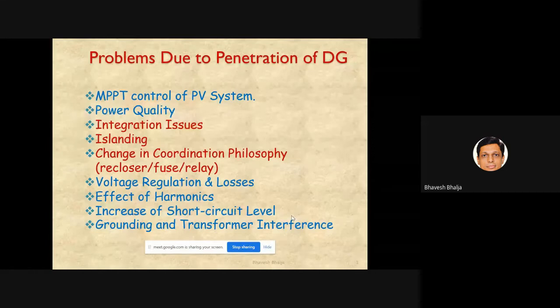The next issue is the increase of short circuit level. Let's say DG is not connected. Then obviously at a particular bus, if you measure fault MVA, I don't know whether you have done it at UG level, you have studied the fault calculations, right? There you have calculated the fault analysis and obtained the fault MVA at a particular bus. And that MVA is responsible for deciding the capacity of circuit breakers.